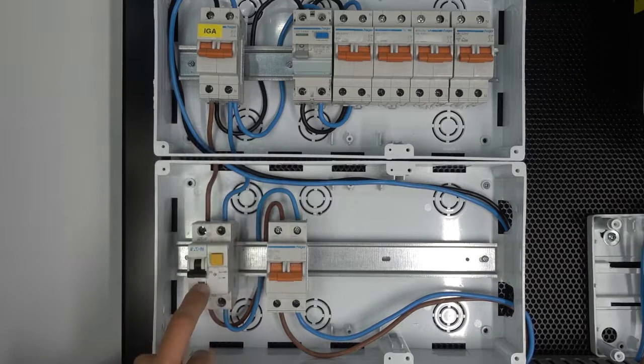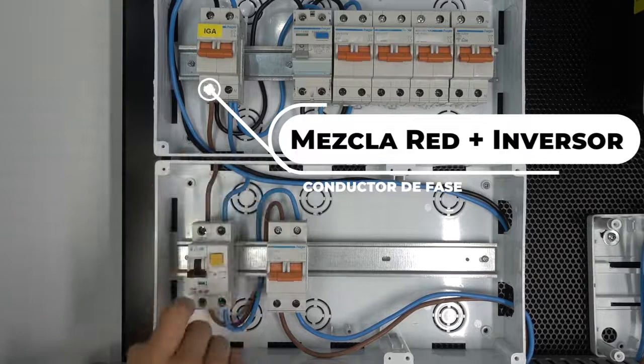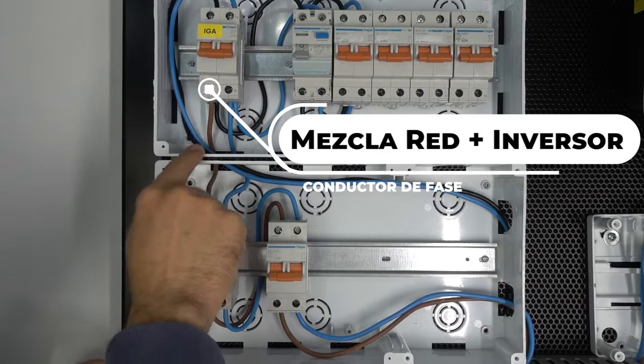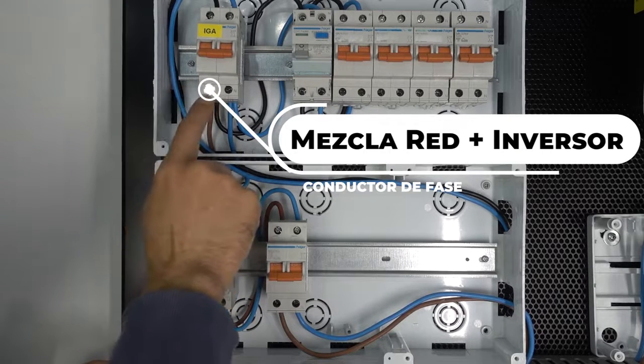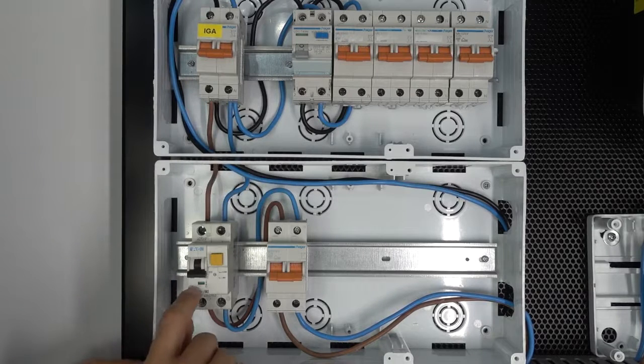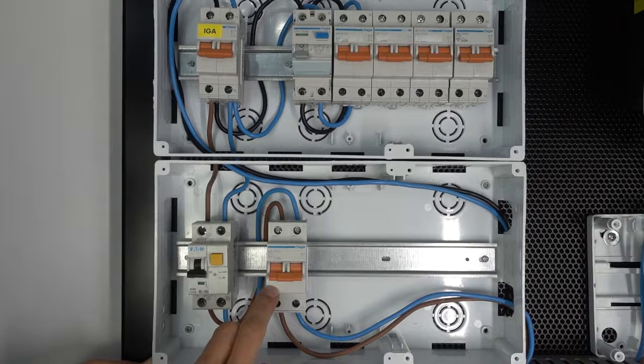Well, here you can see that we have already connected the protections that go to the inverter. We have connected the phase, the brown wire, and the neutral wire that comes out of the main circuit breaker, downstream of the main switch of the house. We have taken it to this differential that is recommended to be of type A. We will see a little bit next the values of both the differentials and the magnetothermics. And then as you can see, it already passes through the circuit breaker to go towards the grid inverter.